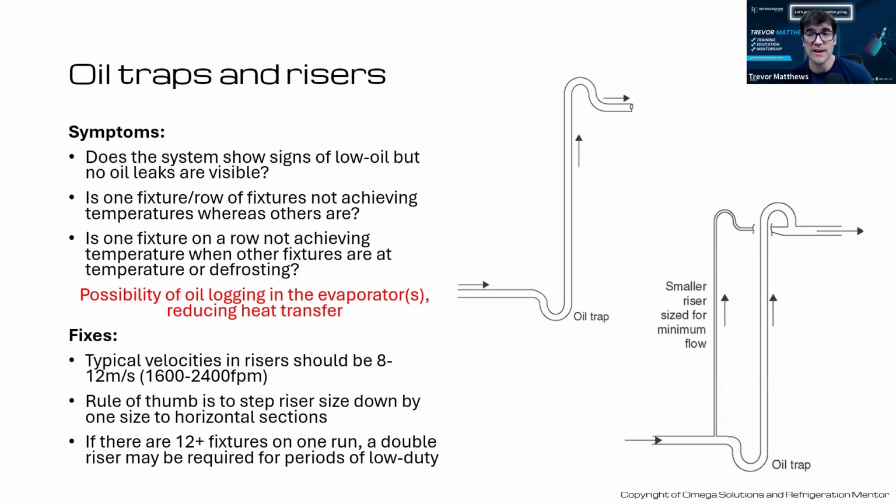Sometimes it's not, if it's in the attic or on top of a walk-in box, but most of the time it would be an obvious oil stain somewhere. But if you don't see any of that, that oil's still in the system somewhere.